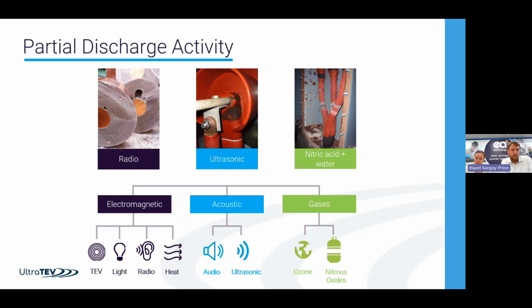And finally, there are gaseous byproducts produced that will eventually cause nitric acid and other things in the local area. The concentration of these can build up - if you walked into a substation and smelt ozone, that is probably from PD activity, or certainly some sort of arcing. They can get to that level of concentration, but generally the moving air through these outdoor sites means the other techniques are more preferable.